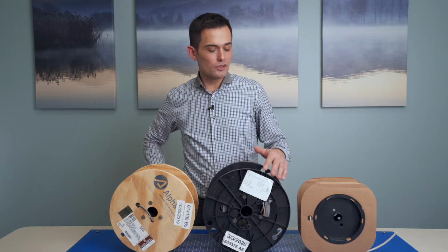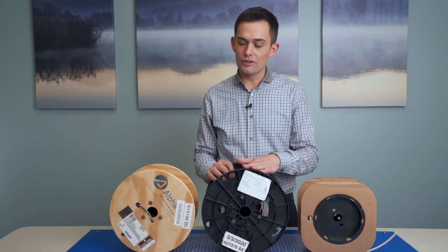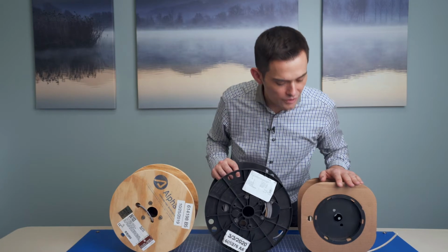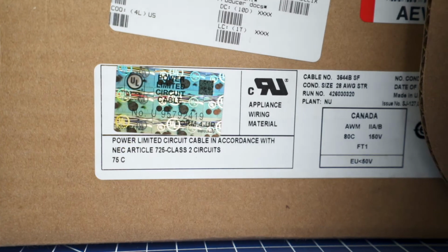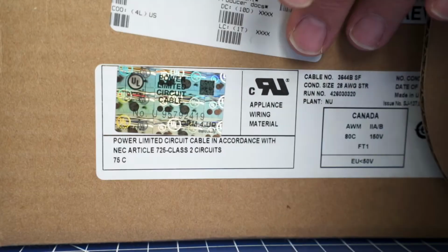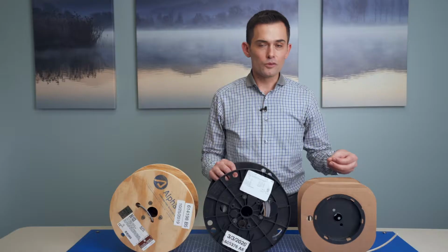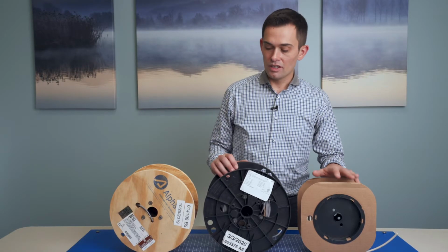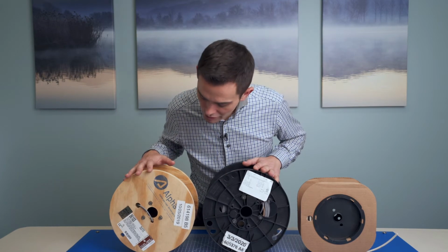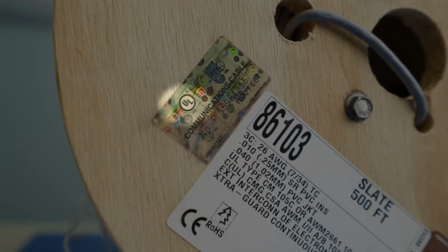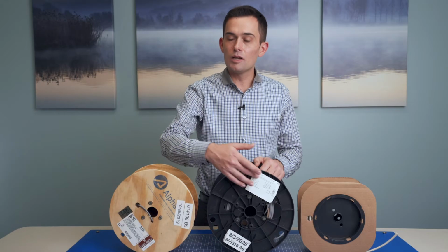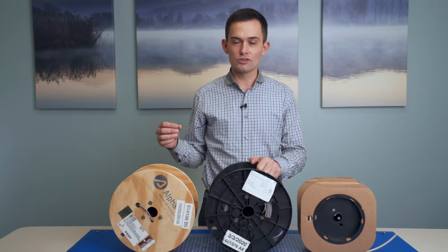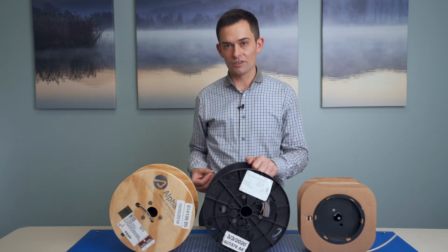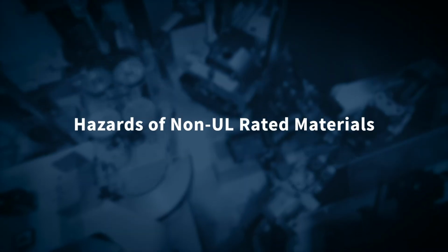environment. So here we have a few different cable spool types and they all bear different UL markings. The first one has this backwards RU symbol, which indicates that this is a UL recognized component. It's not listed. It's suitable for general purpose use. It hasn't been tested for specific environmental hazards. These two over here do have the logo that people are more familiar with, the actual UL symbol. Anytime you see a UL symbol, that means it's an actual listed product, which means it has been tested for specific hazards.